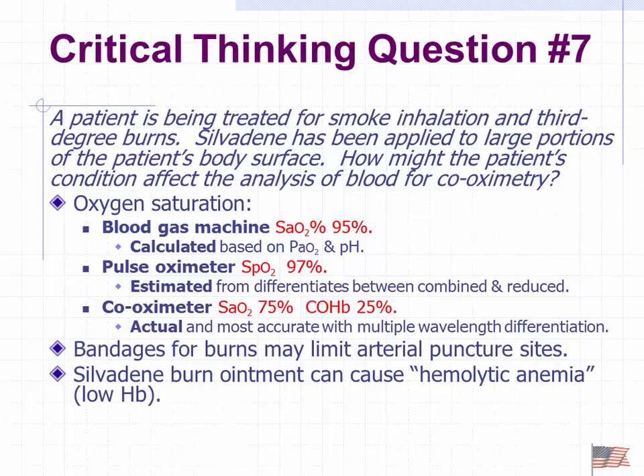I don't know how many times we've kind of covered that point, but I will guarantee you will see at least. Repeat that one more time. Absolutely. If we have a patient we suspect has been exposed to carbon monoxide for whatever reason, either a fire or they were found inside a vehicle running inside a closed space, attempt suicide, you want to use a CO oximeter. You don't want to use a pulse oximeter or the saturation that would be derived, not measured, derived from an ordinary blood gas machine, because it can calculate it based upon some tables. I don't want that.